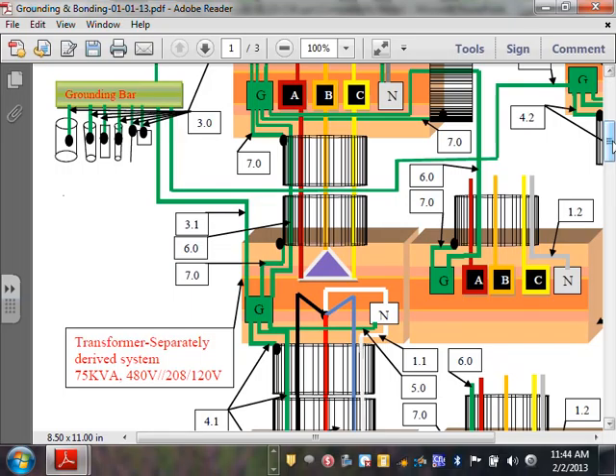Okay, but think of it as redundancy though. If you're to lose one, you have another path. So think of it as redundancy. Any comments, guys? Any questions? Yes, sir. This one? Yeah, it will be inside the switch gear. Then you have to pull another conductor, basically. You pull one inside the pipe and one outside the pipe. Can I put the two of them inside the pipe? Yes, but typically one inside, one outside the pipe, going to the grounding electrode system inside the switch gear, which is funny. I see your point.